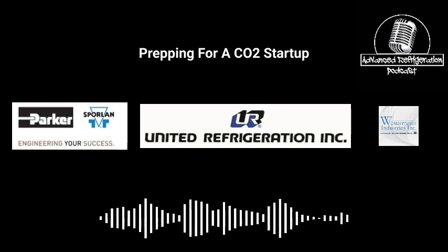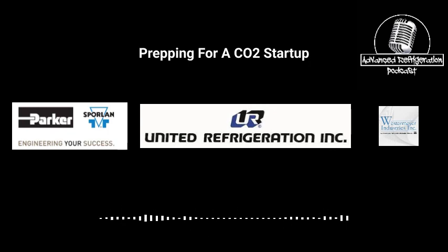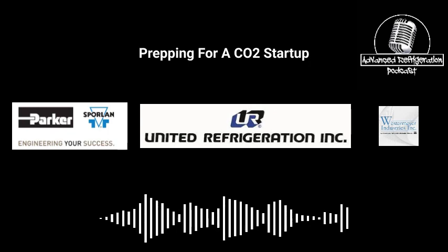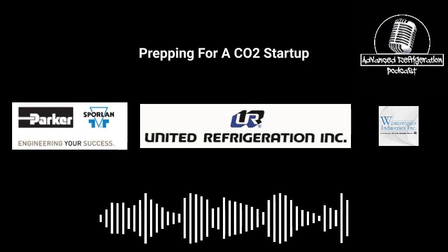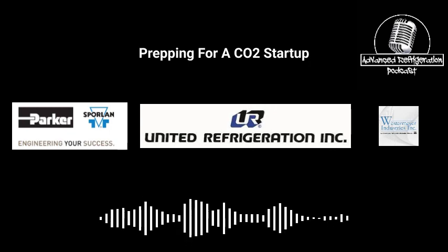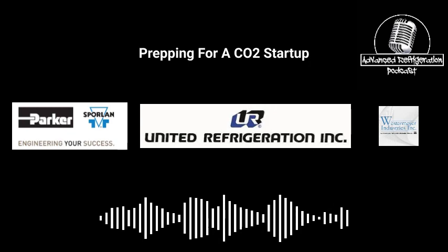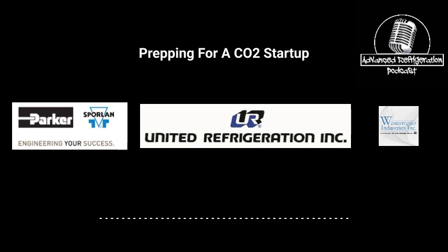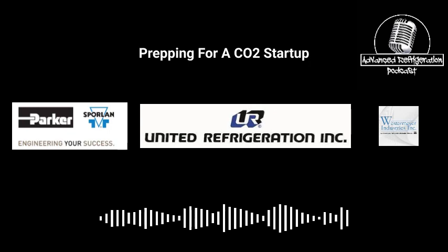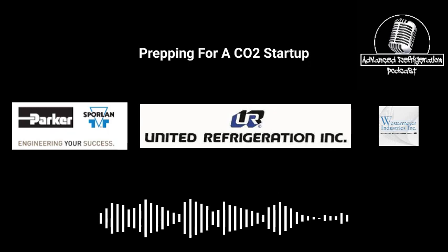So say we're pressurizing a rack for a leak check, we're trying to make sure we're bringing the whole rack up to like 550 pounds, and we're letting it sit for like 24 hours. If you have a leak in the rack, you are screwed, because if you have the cases, if you have the store valved off from the rack, just to make sure that nothing is going anywhere, it will bleed backwards into the rack because of the check valves. So if the cases are higher pressure than the rack, it's going to bleed backwards. So that's where this whole thing gets super tricky.